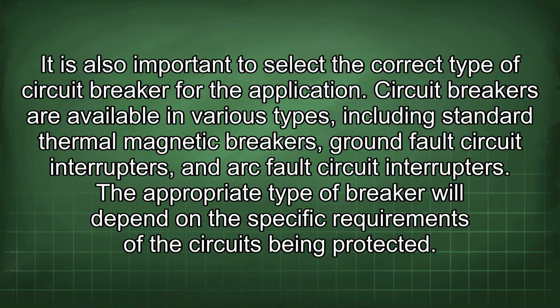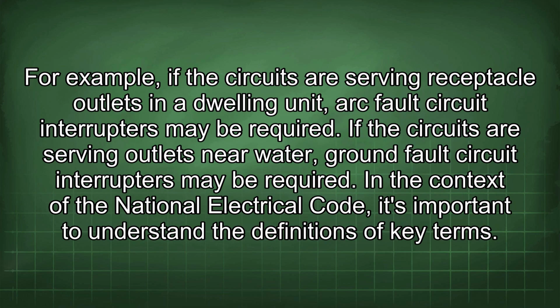It is also important to select the correct type of circuit breaker for the application. Circuit breakers are available in various types, including standard thermomagnetic breakers, ground fault circuit interrupters, and arc fault circuit interrupters. The appropriate type of breaker will depend on the specific requirements of the circuits being protected. For example, if the circuits are serving receptacle outlets in a dwelling unit, arc fault circuit interrupters may be required. If the circuits are serving outlets near water, ground fault circuit interrupters may be required.